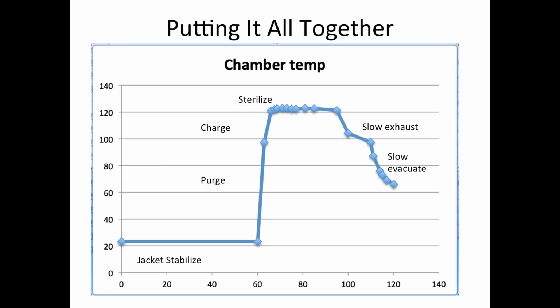So let's put it all together and look at what happens to the chamber temperature during the run. Now look at the jacket stabilize phase of the run. Remember, at this point, we have not admitted any steam into the sterilization chamber. We only want the chamber temperature to be stable when we do admit the steam during the purge and the charge phase. At that point, when the charge phase is complete, we are at our sterilization temperature.